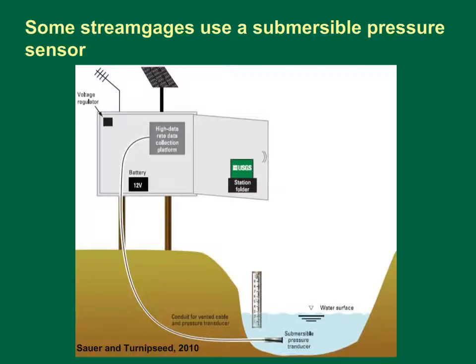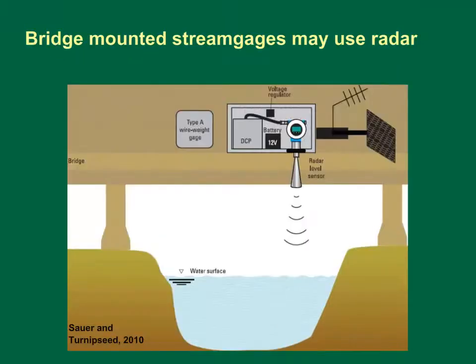This schematic diagram shows a stream gauge with a radar level sensor that is used to measure stream stage by measuring the distance from the radar unit to the water surface. This type of gauge is designed to be used for measuring stage from a bridge, usually when the distance to the water is large. As with the previous stream gauge, the electronics are powered by a solar battery system, and measurement results are transmitted via satellite or cell phone. This type of stream gauge will have a staff gauge mounted in the stream that is used to manually check the water level to help calibrate the radar unit.